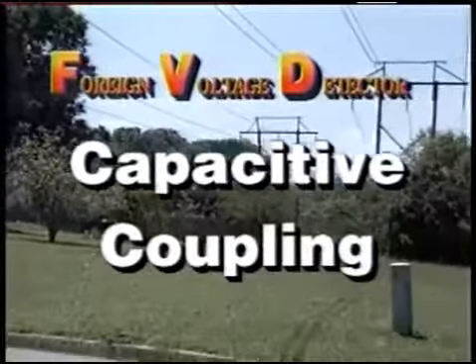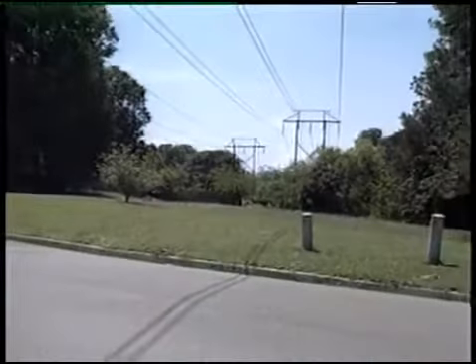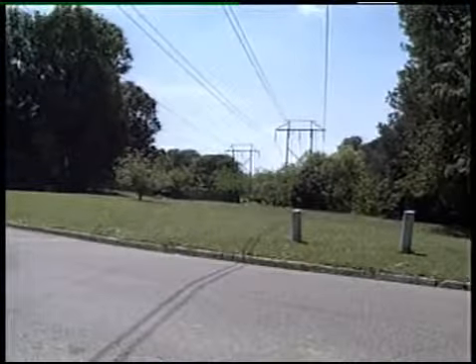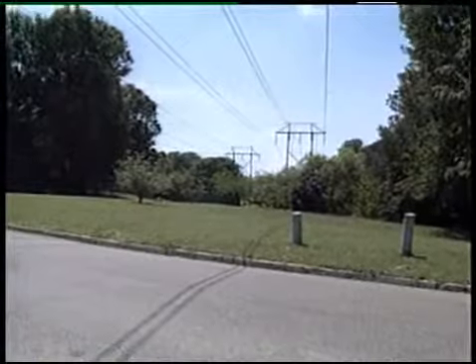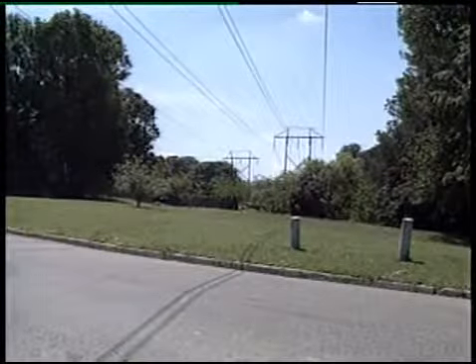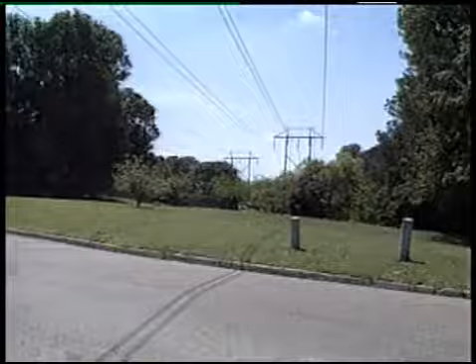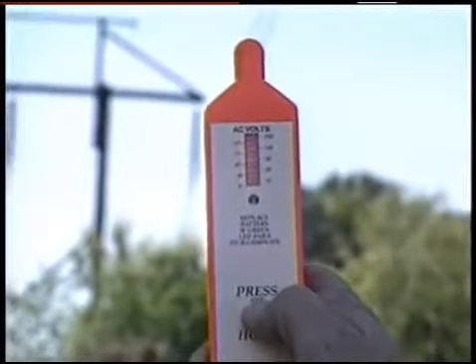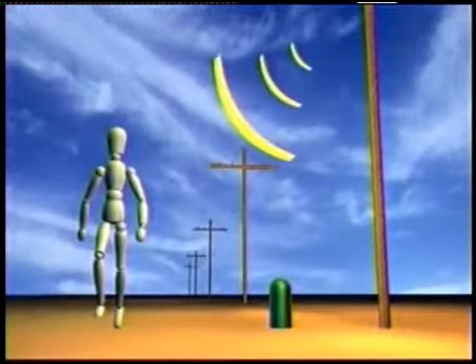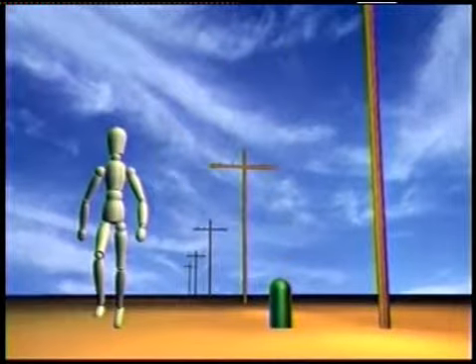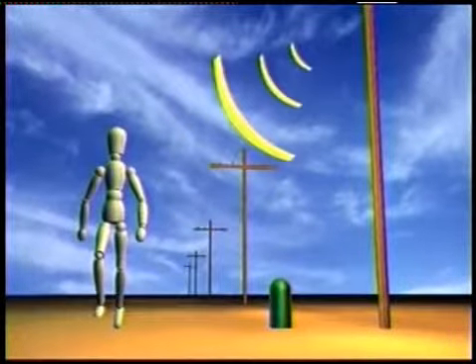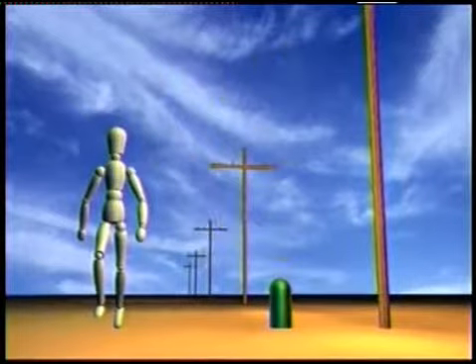At this site, we have a power line operating at 230,000 volts with a telephone pedestal almost directly underneath. This voltage level produces an extremely high electrical field, often referred to as an E field. If we point an F.V.D. toward the line, we get an immediate alarm. If you test this technician, you will find that he is energized. These indications are caused by the electrical field between the power line and nearby conductive objects. These are not false indications. The indicated voltage does exist on the objects.